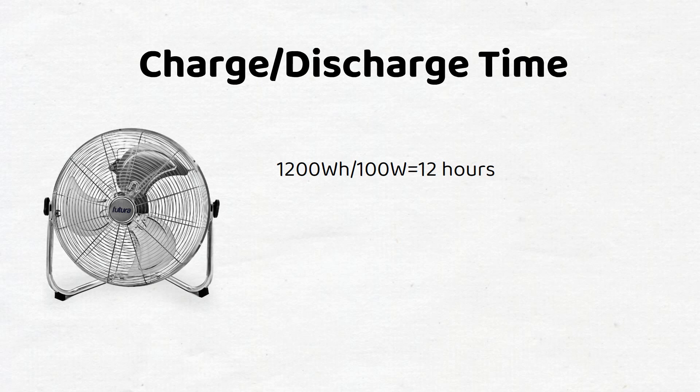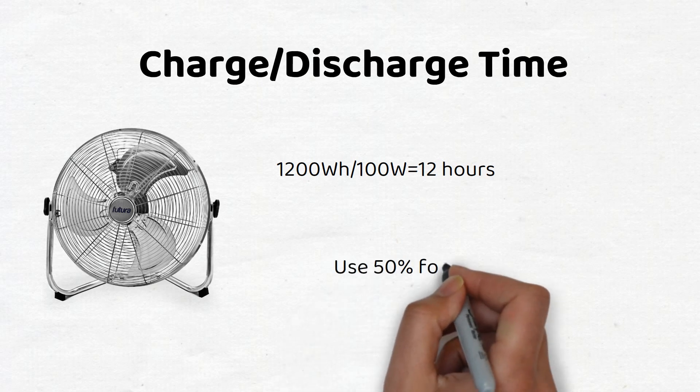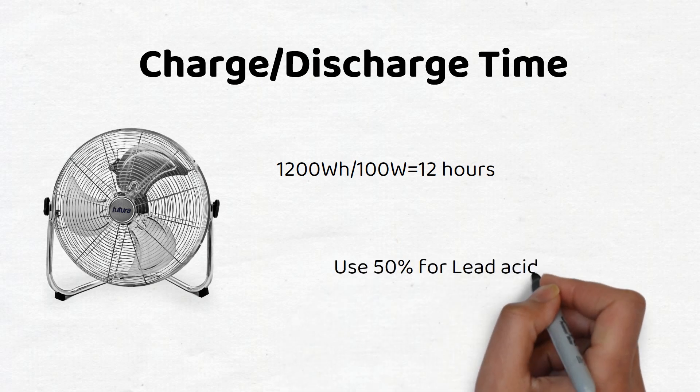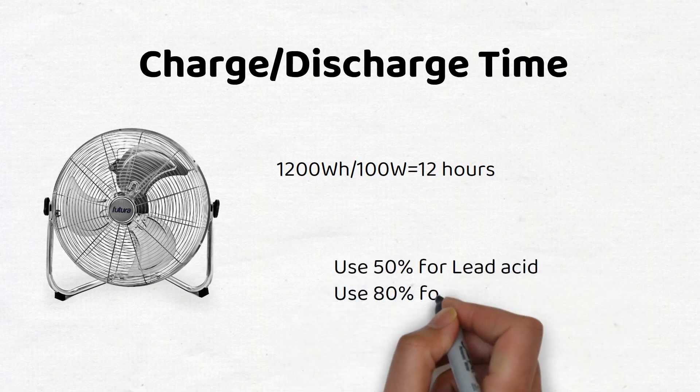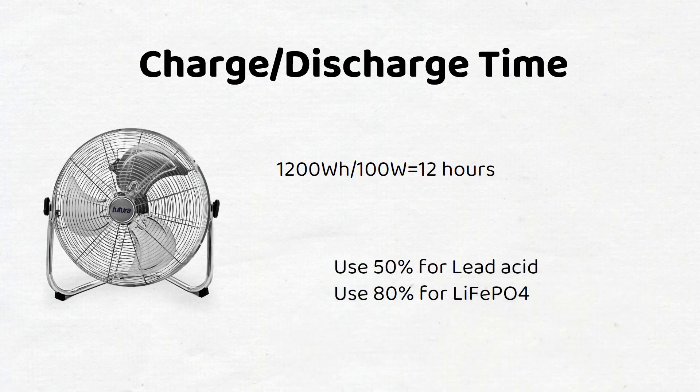I say theoretically because a battery should never be discharged to 0%, whether it be lead acid or lithium. Use 50% of the capacity for a lead acid battery, and 80% for a lithium iron phosphate battery.